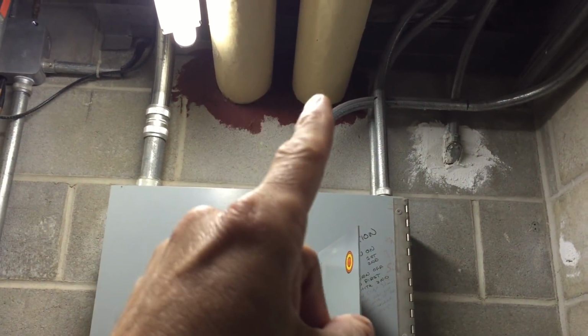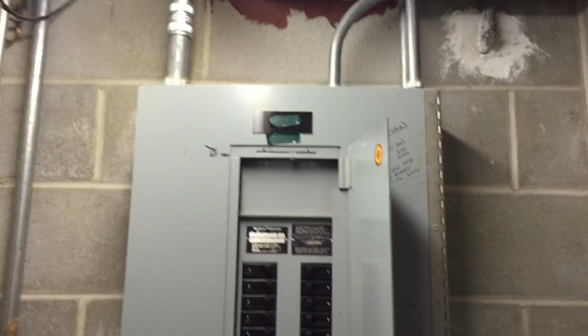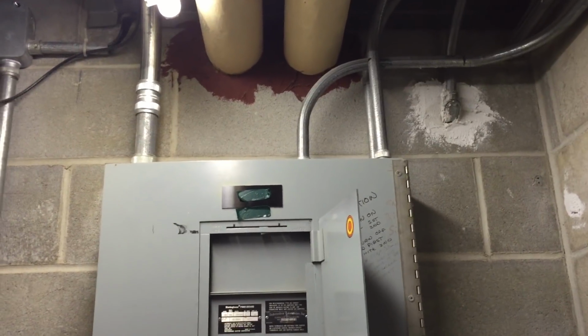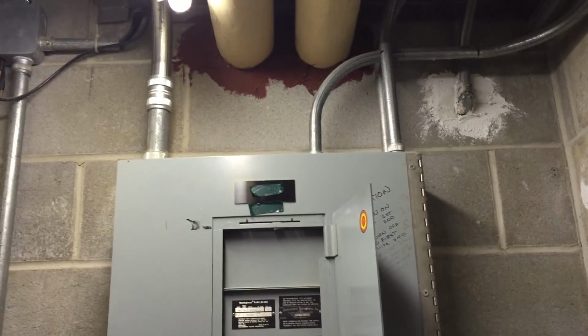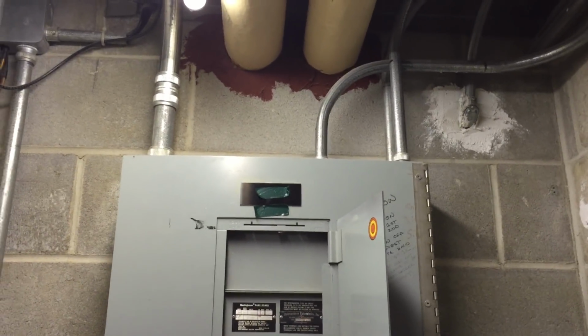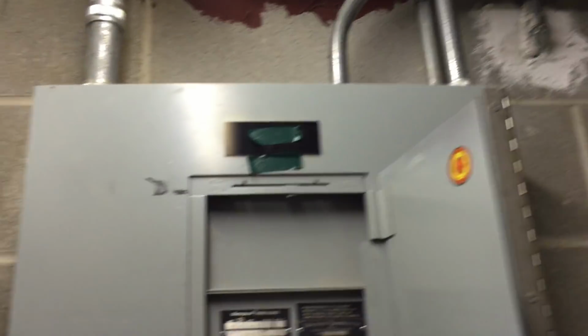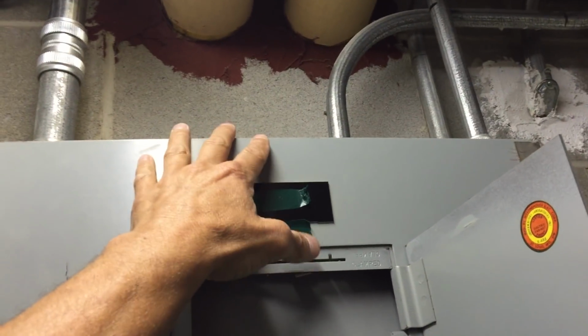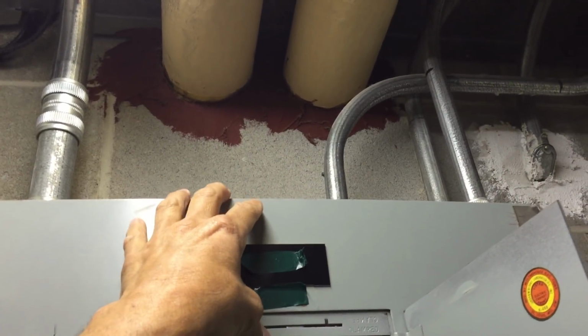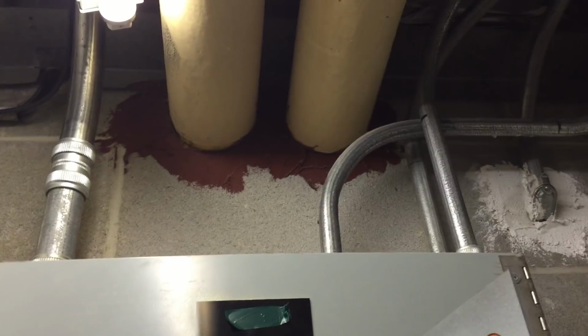What we're looking at here, these two pipes, that one and this one, directly above this panel board, this is a violation of section 110.26E1. Panel boards, switchboards, and motor control centers have to be in a dedicated space. And what that means is the space directly above this panel board, for a height of 6 feet above or to the structural ceiling, whichever comes first, needs to be dedicated to the electrical installation.